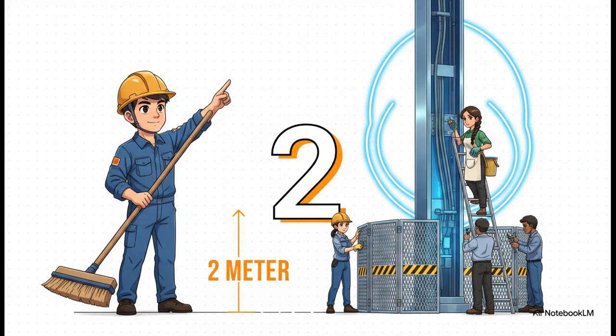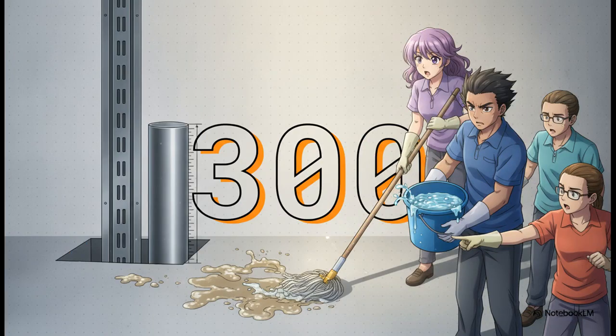Now I want you to burn this magic number into your brain. 2. Rule 12-200 states that if a warehouse worker, a janitor, or honestly anyone unqualified can walk right up to your vertical busway, you must provide mechanical protection up to exactly 2 meters above the floor. This is literally to stop someone with a sweeping broom or a ladder from accidentally knocking into a live, high-amperage busway.